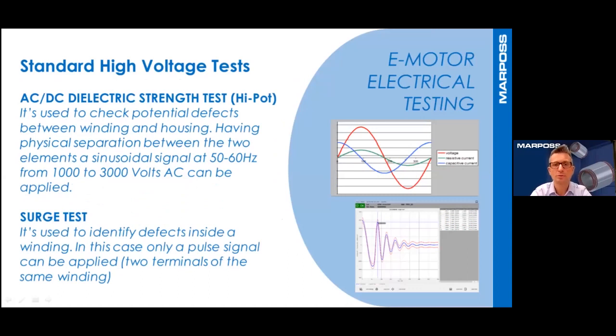Now, a brief introduction to the standard electrical tests for electric motors and their components. The main high voltage standard insulation tests used to identify failures in the motor windings are the AC/DC dielectric strength test, surge test, and insulation resistance test. The dielectric strength test, or Hi-Pot test, is typically used to check potential defects between windings and housing, and also between windings of two different phases, if they haven't a common point. The star point is disconnected.